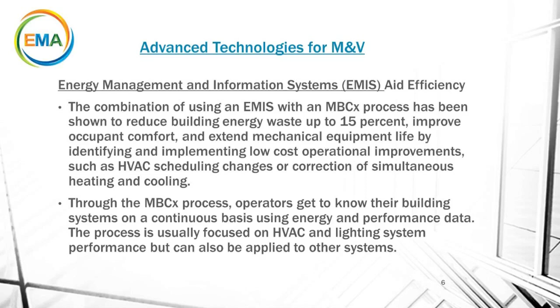Through the monitoring-based commissioning process, operators get to know their building systems continuously. You learn about what's going on during off hours, nights, and weekends, what's happening when no one's there. We don't typically have 24/7 shifts, seven days a week, including holidays. So through this monitoring-based commissioning, if something goes wrong on the weekend, typically Friday night at 2 a.m., you now have that transparency.